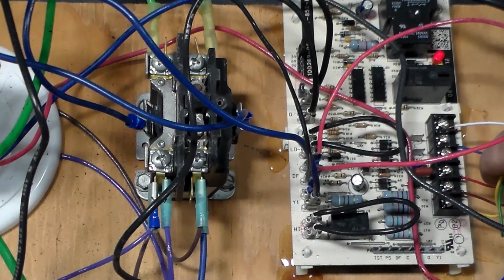R, as we know, that's your red wire, your power, 24 volt. These heat pump boards are powered 24/7, not just during a call. So they're going to have that 24 volts on them to keep track of memory and timing, things like that, because there is a clock built in. You have to keep track of time. So we got to have constant 24 volt power. Then of course we have a C terminal, which is your common.